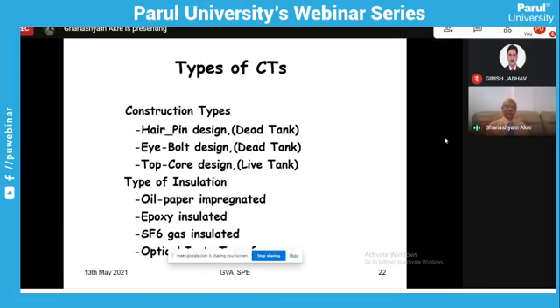Depending upon the insulation, there are different types. One is oil impregnated, oil paper impregnated insulation. Another insulation can be epoxy. Another example can be SF6 gas, which is used very widely in circuit breakers. Now in India also, SF6 type current transformers are already in the market and being utilized. They are very safe. Then fourth is the optical CT, where the isolation between the high voltage and low voltage is perfect, and there is no question of any high voltage failure in this case.